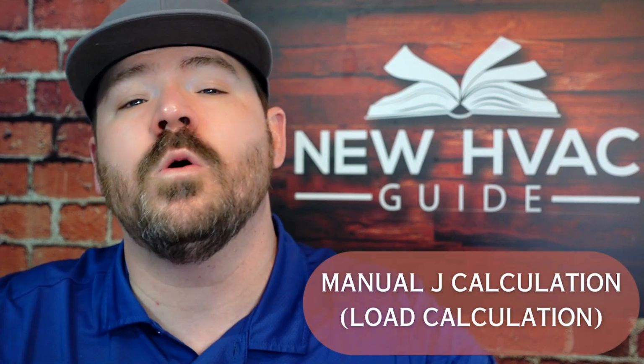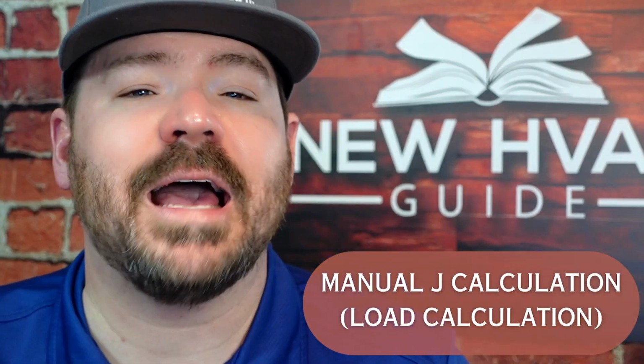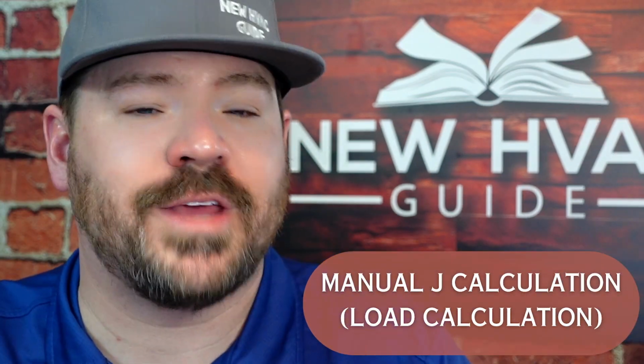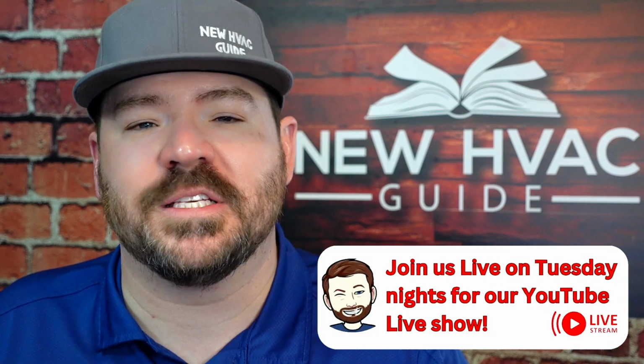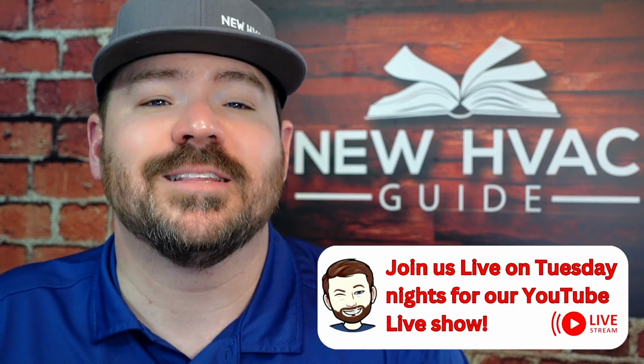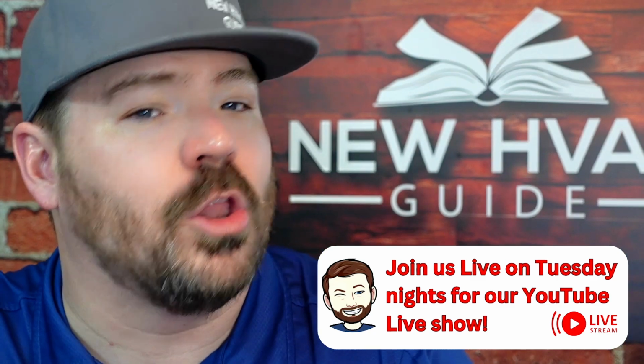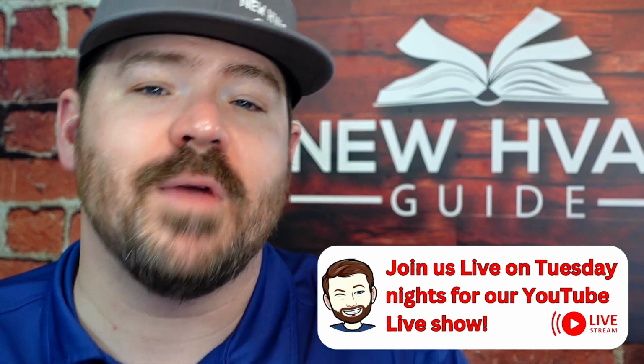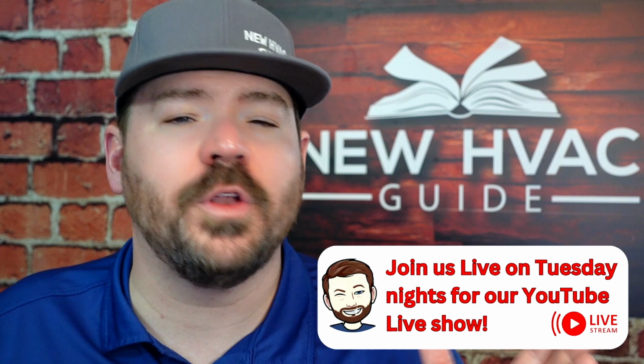There are three calculations. The first is called a manual J calculation—a lot of guys in our industry will call it a load calculation. This matters because a lot of folks think, well, isn't bigger better? If I install a really big air conditioner, it will run, reach temperature, shut off, and I'll save tons of energy. The problem is, without getting too technical about dew point and things like that, the system doesn't run long enough to remove enough humidity from the air, and it creates a whole other set of issues.